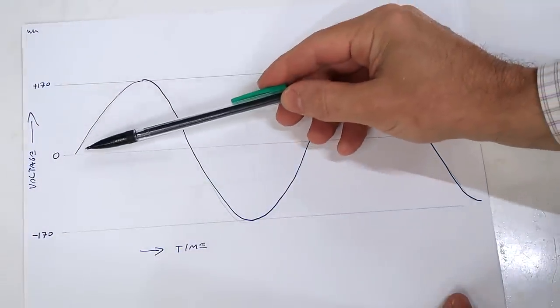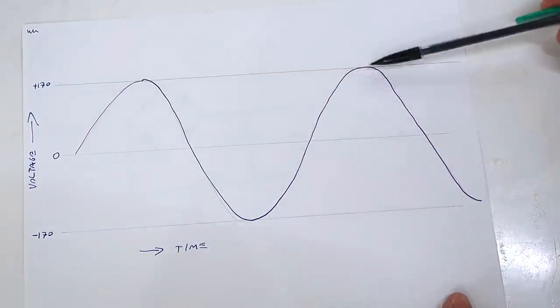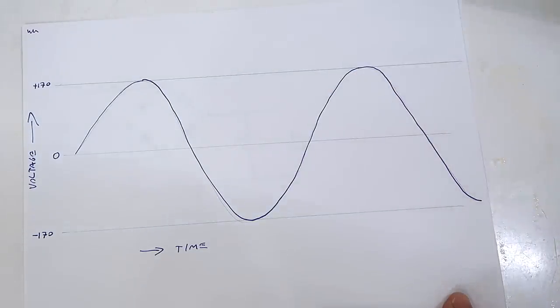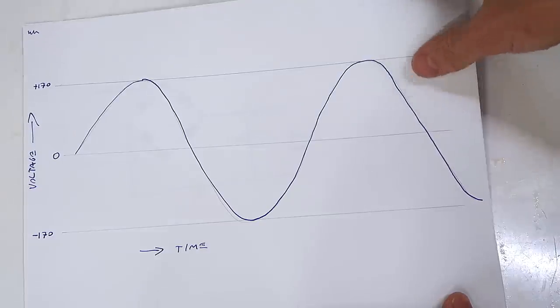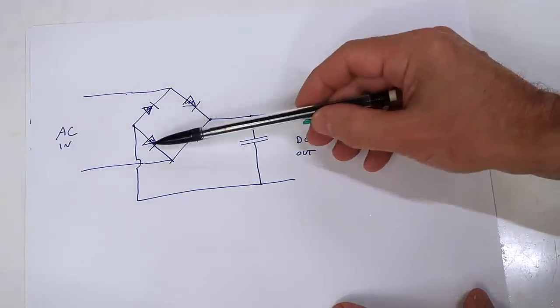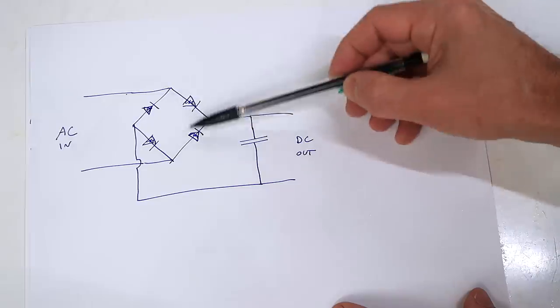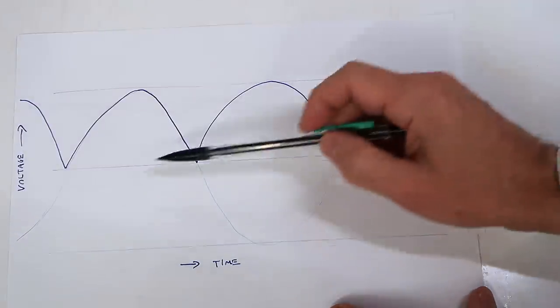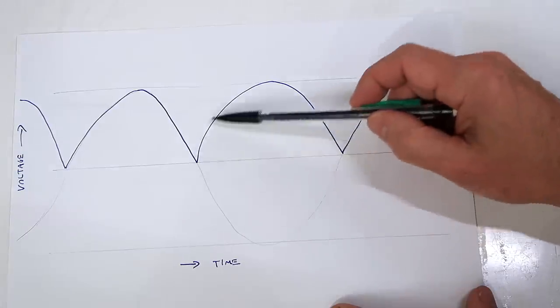The waveform from the power company is essentially a 60 hertz sine wave, 60 times per second, positive, negative, positive, negative. But the mini split, using brushless DC motors, needs DC. So we use something called a rectifier using four diodes that only pass current in one direction to essentially flip the bottom side of this waveform to the top.